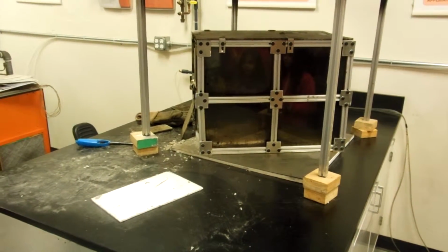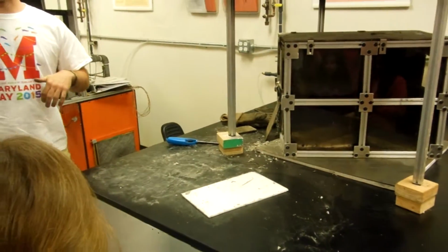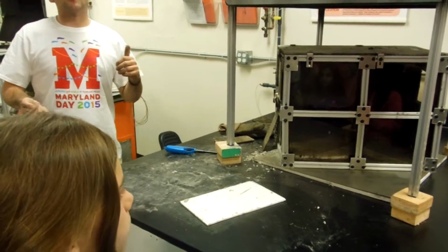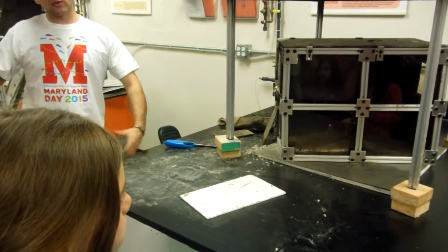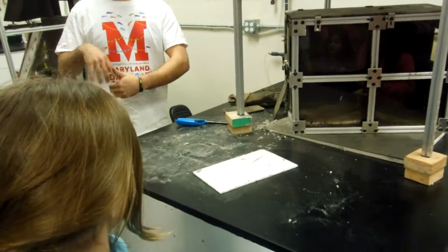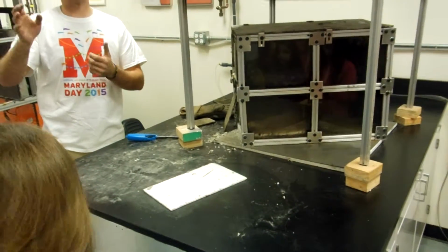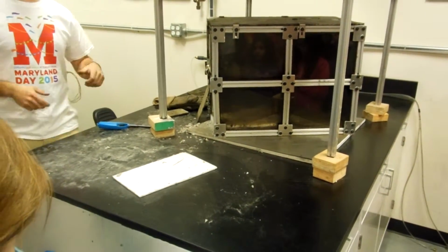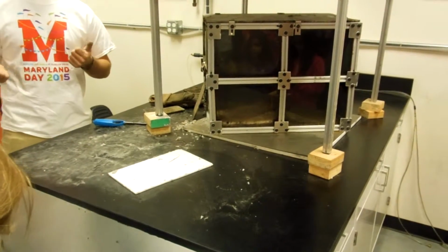There's a fire in here, they were in there, they left, but they forgot to close the door. So we kind of remove that source of error by having those door closers on there, so that if there is a fire here, it stays here. That door is rated for an hour and a half, so if there's a fire in here, we have time for the fire department to come, stretch out their hose lines, and ultimately extinguish it.